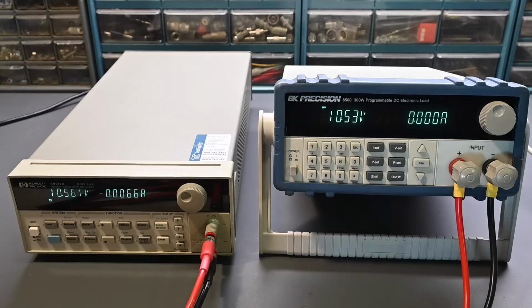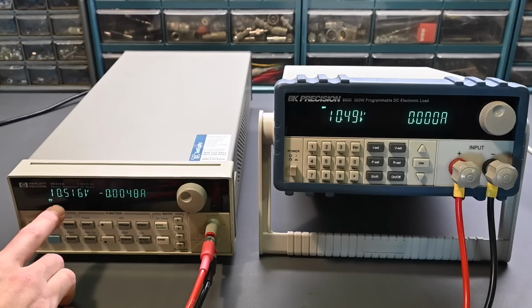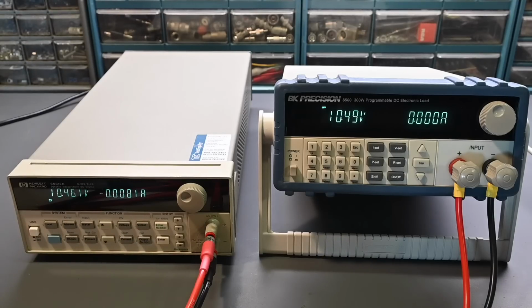Okay, so we actually do have an output voltage, so that's good to see, and it matches 10.53, 10.54. So very, very close on those numbers, no problems there, but that's not what the program voltage is. It should be sitting right at 10 volts. These are very, very accurate power supplies. So this is way off. That's not acceptable, definitely a problem. So it should be sitting spot on at 10 volts, and it's really not stable either. It's kind of hunting around. The values are jumping around a little bit.